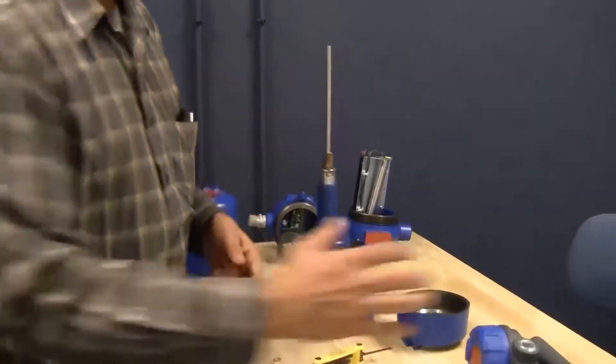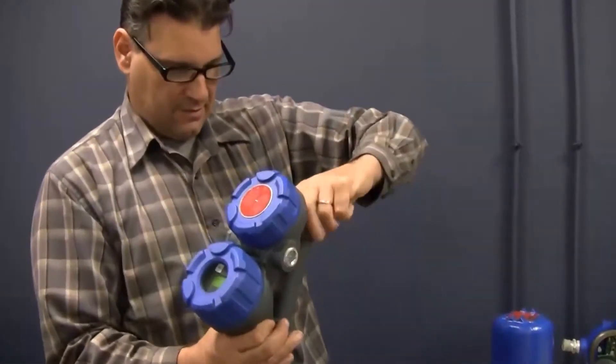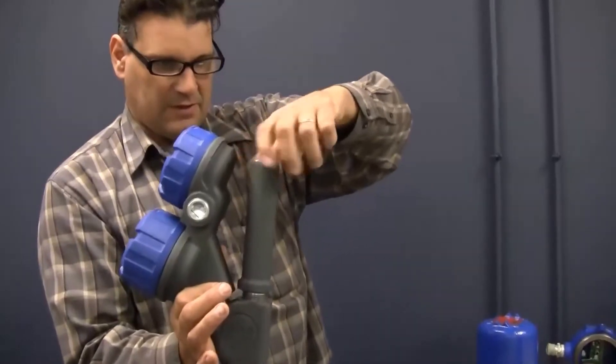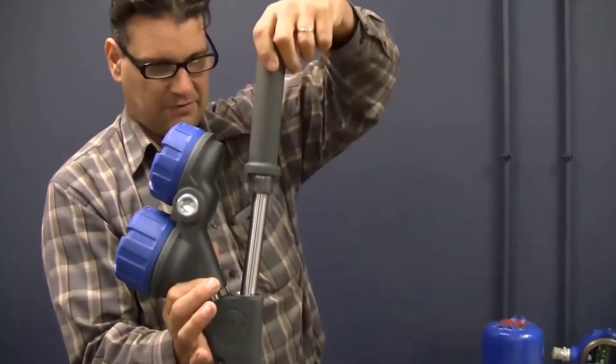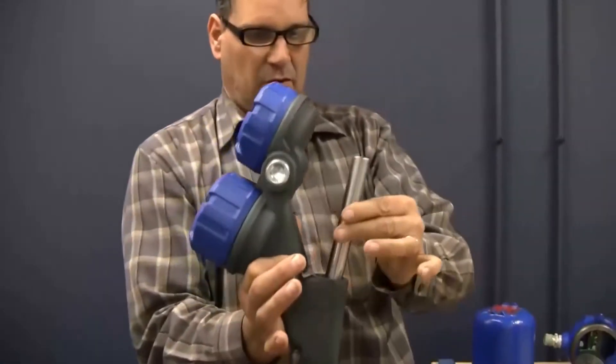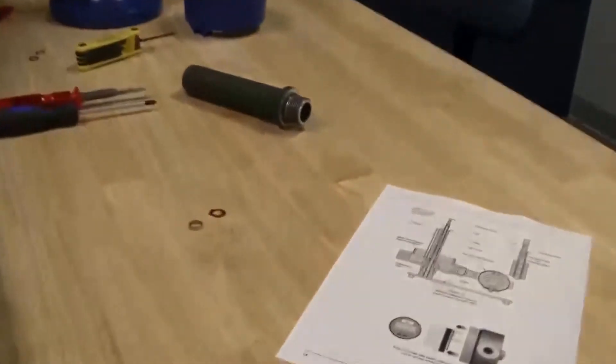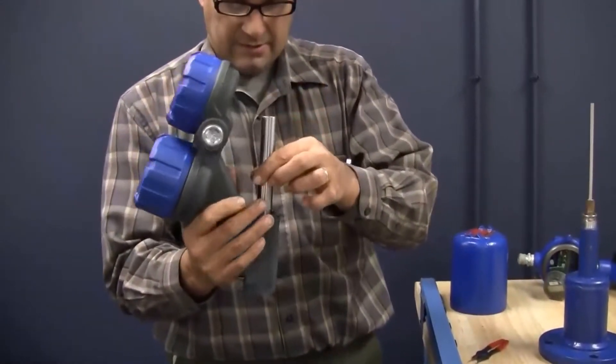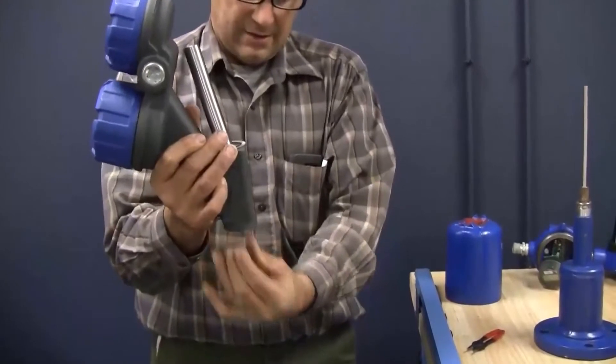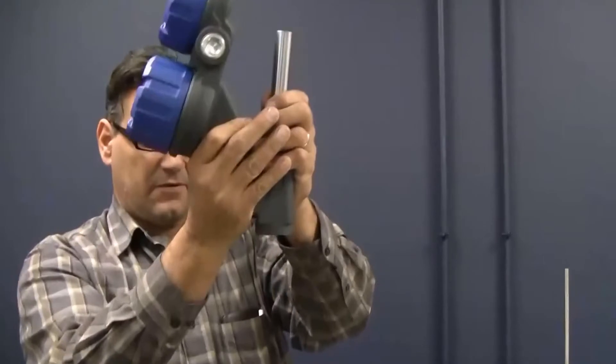So we can now take our new E3 head and remove this. There's not going to be an enclosing tube inside there. There will be what we call a fake enclosing tube that's holding the cell LVDT and the little washer and C-clip in place. So be sure to remove the washer and C-clip, and pull the fake enclosing tube out. And this is simply going to slide back on where the old one was.